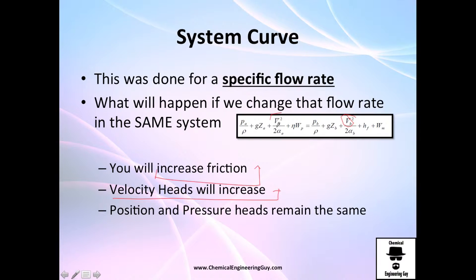The velocity heads, by definition, these little guys right here and here will increase. The only case in which you will not increase will be when you are moving from static to static - here velocity of A is zero and velocity of B is also zero, so the only thing that will change is the friction.